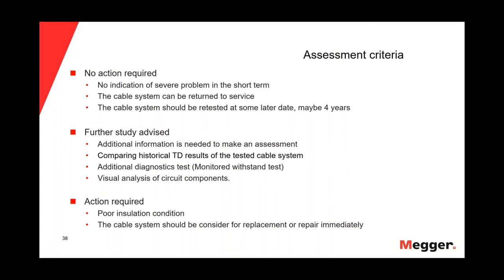Action required means we have a poor insulation condition and the cable system should be considered for replacement or repair immediately. What is very important to know: we should never make a decision — especially never decide to replace a cable — based on a first-time tan delta measurement. We always need to wait for at least two or three measurements before making a decision.